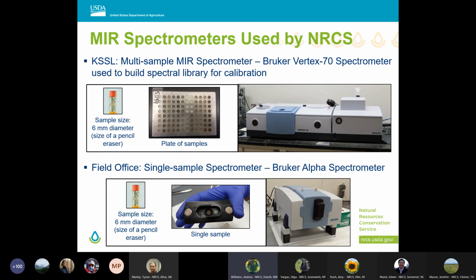The Bruker Vertex 70, shown in the upper panel, is used at KSSL to build our national library of MIR spectra, which the local NRCS field offices use to build calibrations for estimating properties in soils in their local areas. The Vertex 70 has a high throughput accessory that allows it to scan many samples per day. Once calibrations, or the models that are built using the Opus software with Quant 2 package, are made, unknown soil samples collected in the target area can be MIR scanned at the field office using that single sample Bruker Alpha spectrometer shown in the lower panel. That Alpha spectra are then processed through the aforementioned calibrations to rapidly estimate soil properties.